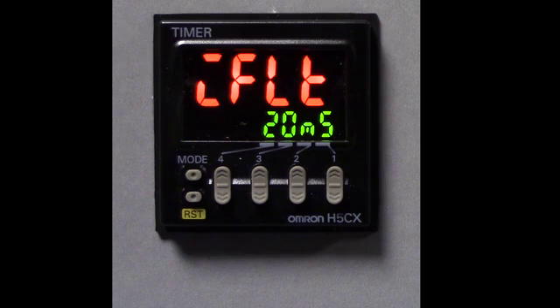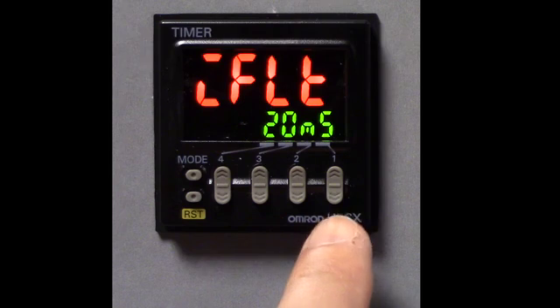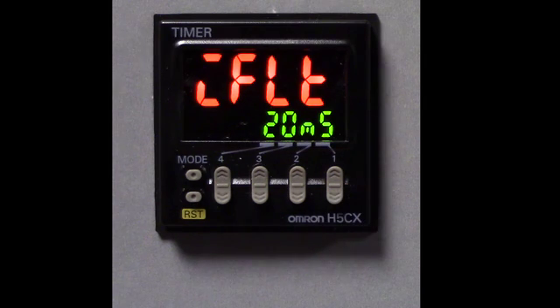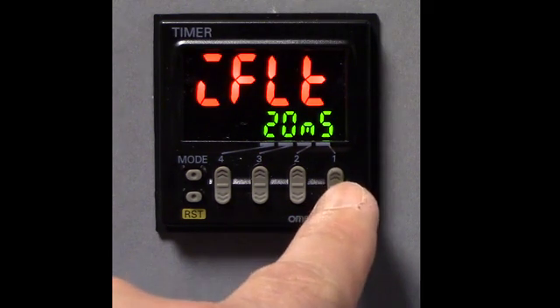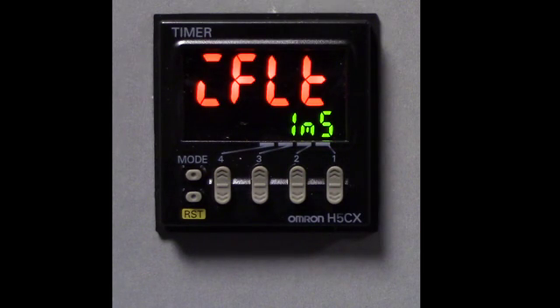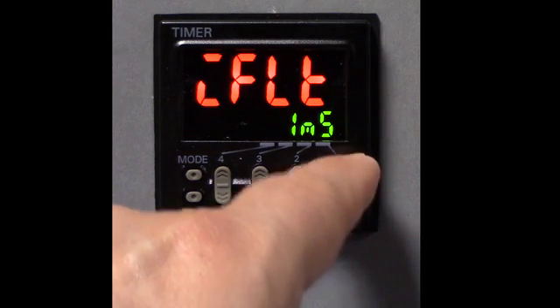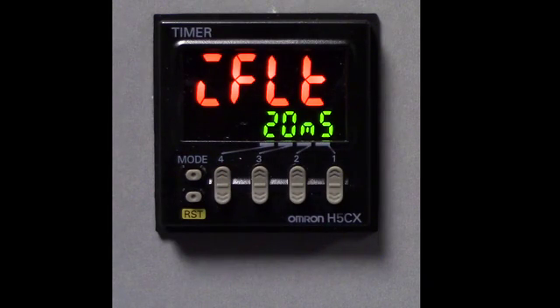IFLT, this functionality will let you determine what input signal you need to use. Since we are going to be using a basic switch, we could keep it at 20 milliseconds, but if we have an input that's very high speed switching, we could change it to 1 millisecond. If you are using a photoelectric or a proximity sensor, you can actually keep it at 20 milliseconds. As I mentioned before, a lot of our customers, when using the H5CX-N timer, use the factory default for a lot of their parameters.